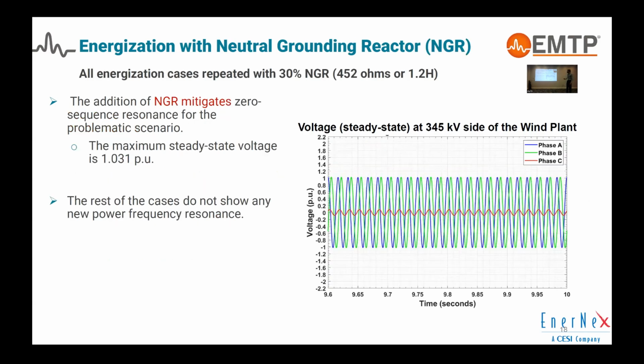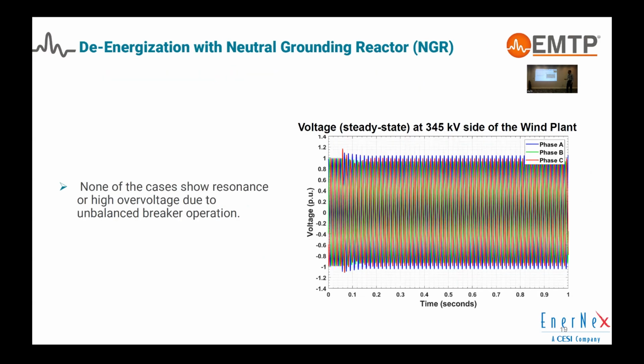So we applied a 30% neutral grounding reactor and reran the simulation, and you can clearly see that now the red phase voltage is pretty small. Also, the addition of this neutral grounding reactor did not introduce new resonance conditions, which was good. And in the de-energization cases, we didn't notice any significant issue with any of the cases.